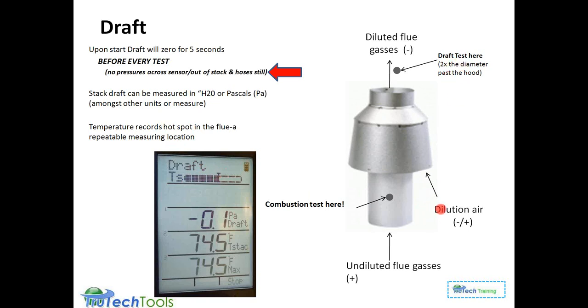This is showing a dilution thimble, but to give you an idea of the importance, as a clear illustration, you have the undiluted flue gases coming up, and you'd want to do the combustion test before dilution if you have an atmospherically vented or a dilution air type system. Because if you did the combustion test afterwards, you would be seeing values that are diluted and not representative of what's going on in the combustion process. It's kind of like putting a lead plate across your x-ray subject. You're not going to see much if you've masked it with dilution air, because so many of the gas parameters depend upon their concentration. So if you've added dilution air, you've lowered the concentration, really fuddled up the flue gas reading.